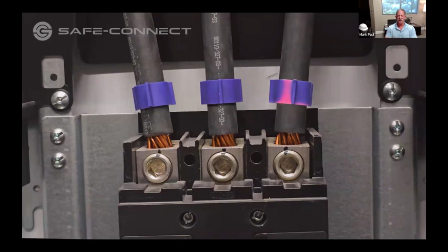This is a visual indication—time lapse sped up—of three conductors coming into a disconnect or circuit breaker. The one on the right went through maybe a heavier load, whatever caused it to change color, and that clip went from purple to pink. Even when the temperature is brought back down, it stays in that exact state. So you can look at it five months later and say, at some point there was a problem on this phase, and we need to look deeper into it and monitor it more closely.